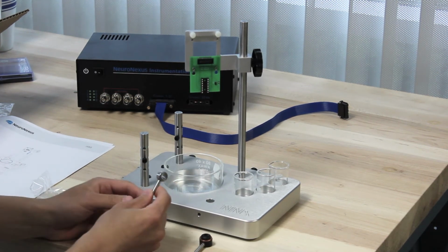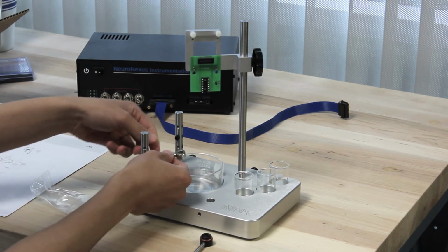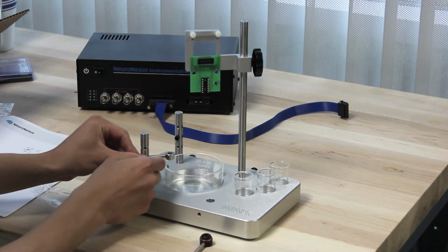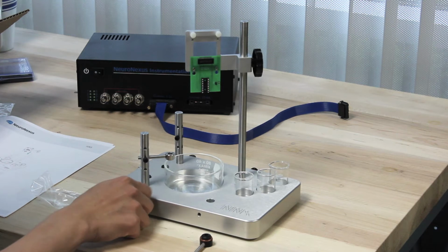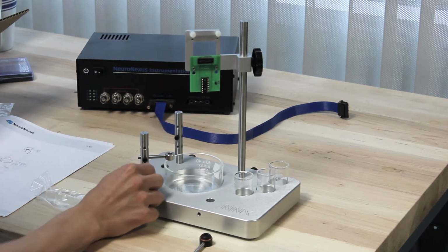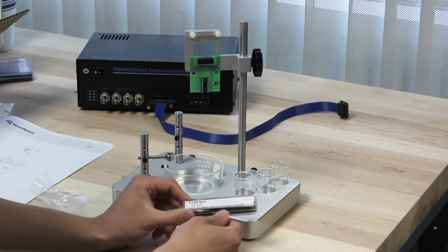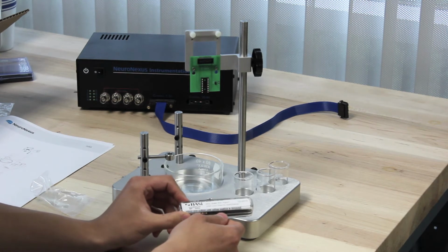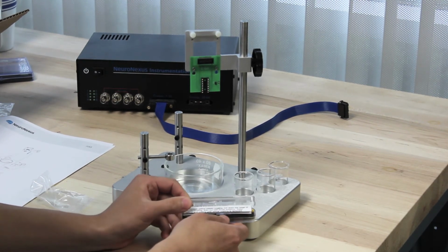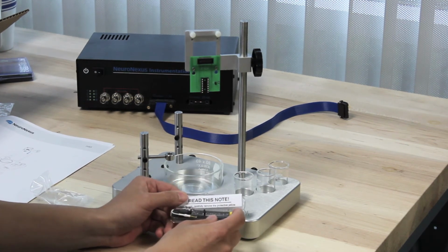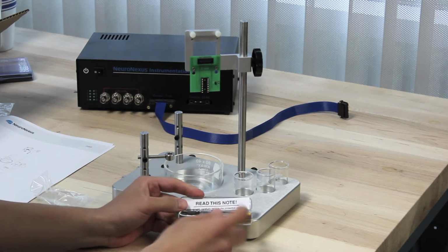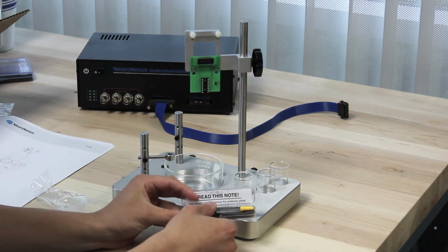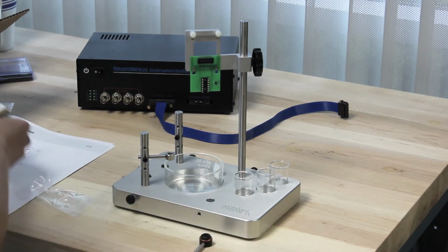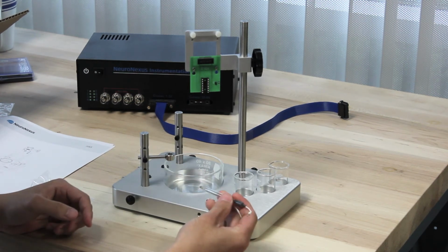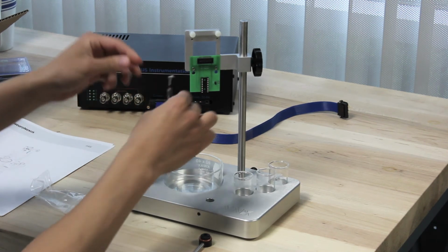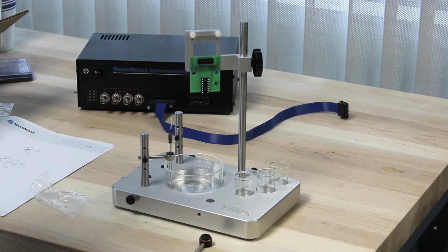First, let's do the reference electrode. Place the holder into one of the small slots. Lock using the set screw here. You might want to tighten this down too. Then take your reference electrode. This is the silver chloride reference electrode that comes with all NXS, and it comes with a special yellow coating at the bottom that protects the frit so it doesn't dry out. Please read the direction that's in the kit on how to remove this. Once you remove it, you'll have a reference electrode that looks like this. Adjust the O-ring for the right height and then place it into the holder.